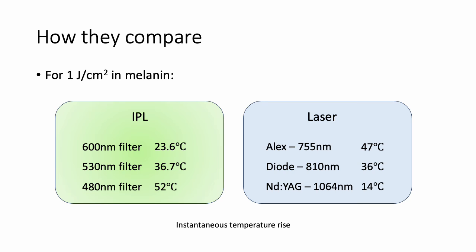For lasers, the Alexandrite laser at 755 nanometers — 1 joule per square centimeter in melanin — will generate a 47 degree increase in temperature, which is quite high, because melanin absorbs pretty strongly at 755 nanometers. For a diode laser at 808 or 810 nanometers, the absorption is not so strong, so the temperature rise is about 36 degrees centigrade — equivalent to IPL using the 530 filter. The Nd:YAG laser at 1064 nanometers will only generate about 14 degrees Celsius because the absorption by melanin at that wavelength is so low. This is why Nd:YAG lasers need to use high fluences to achieve any kind of results.